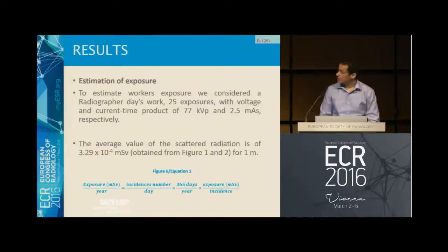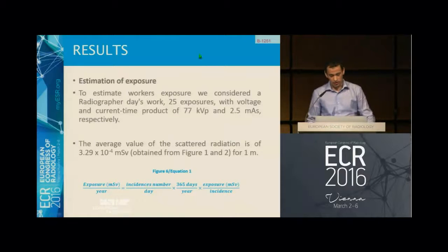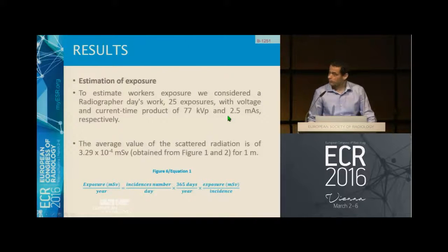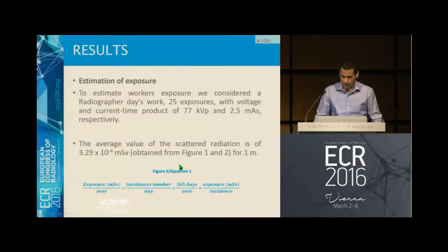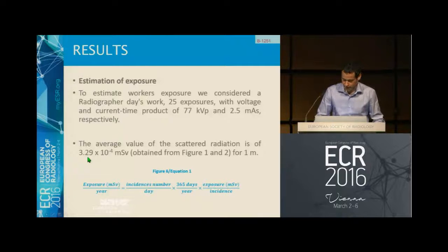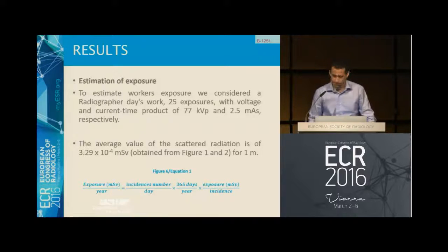We also did an estimation of exposure, considering a radiographer's day's work of 25 exposures with these parameters. We obtained an average value of 3.29 times ten to the minus four millisieverts, obtained from figures one and two at one meter.